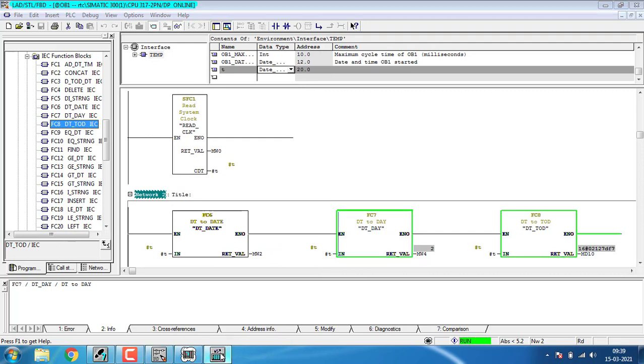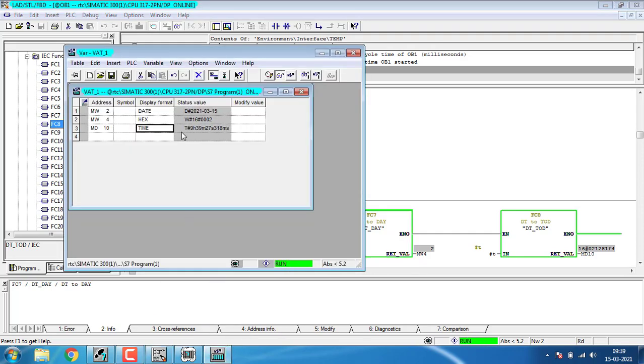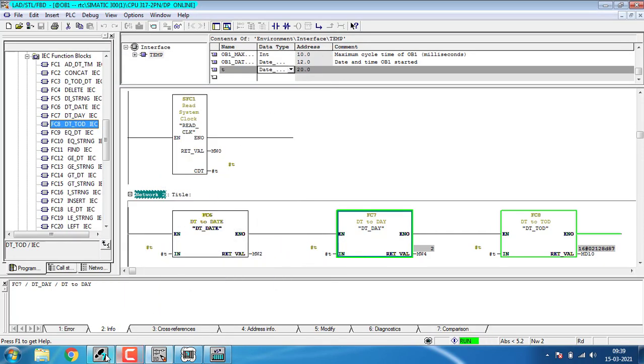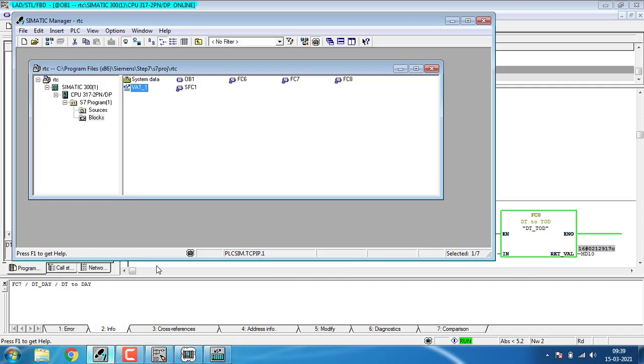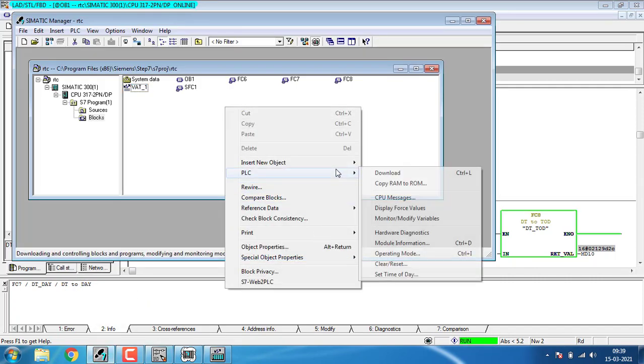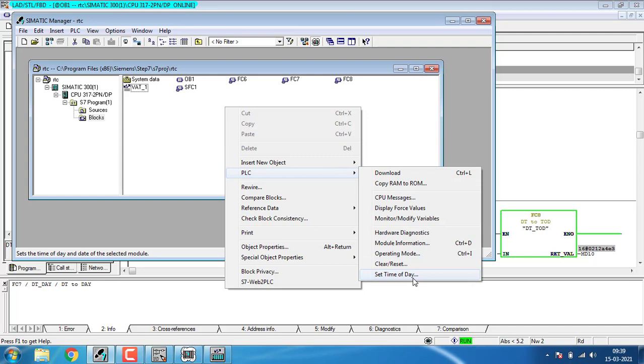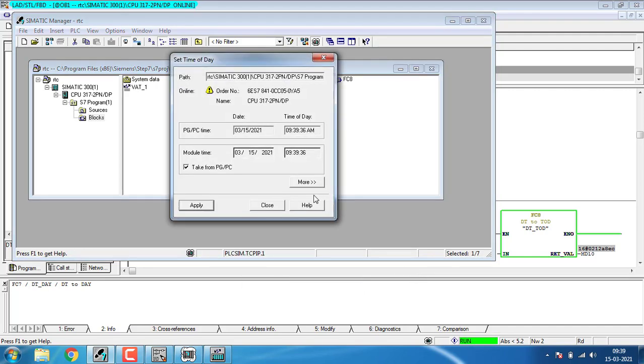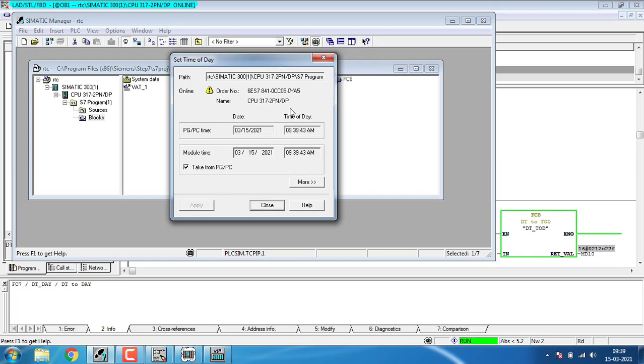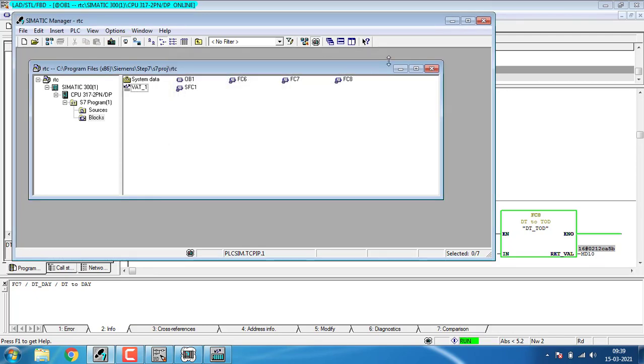We're getting the time and date in the value table. To adjust the date and time, go to the SIMATIC manager, right-click, PLC, and Set Time of Day. You have to set the PG/PC time and the module time, then apply. We can control the date and time of the PLC from these three blocks.